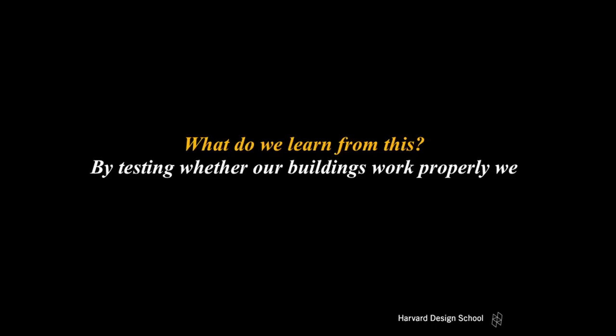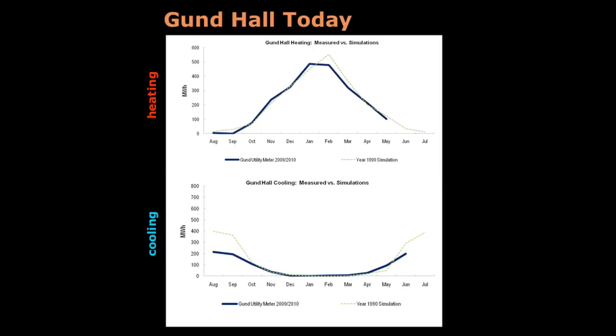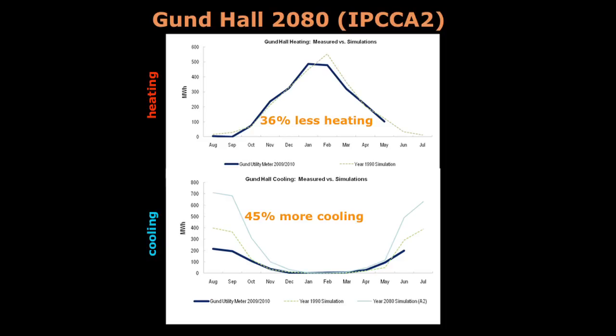What do we learn from this? By testing whether our buildings work properly, we can save a whole lot of carbon and energy without really any costs. We can also use the same technology to look into the future, piggybacking on Professor McCarthy's work to predict for different scenarios the climate of the planet. There's a process called morphing where we combine weather data currently used for building models with future climate scenarios, allowing us to predict what might happen. Applying this to Gund Hall, our calibrated model shows that by 2080 under the A2 scenario — which is more middle-of-the-road — we'll be using 36 percent less energy for heating and 45 percent more for cooling.